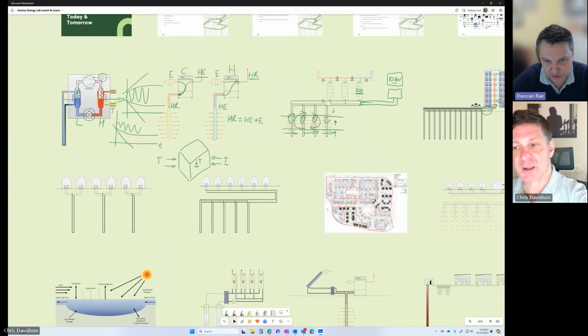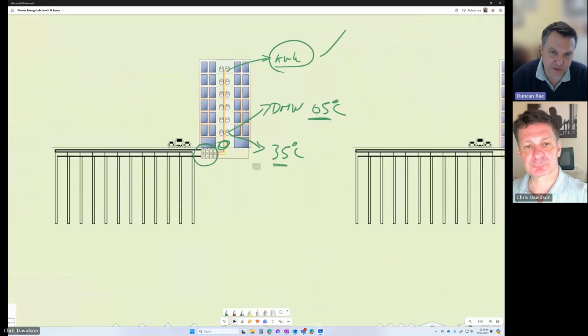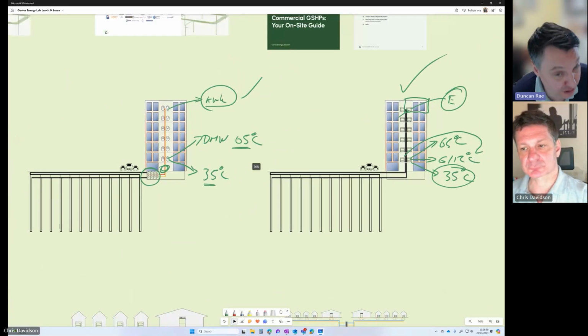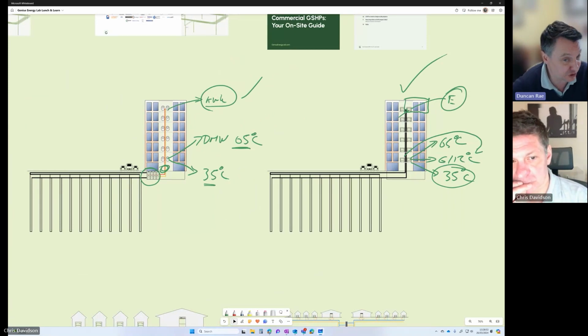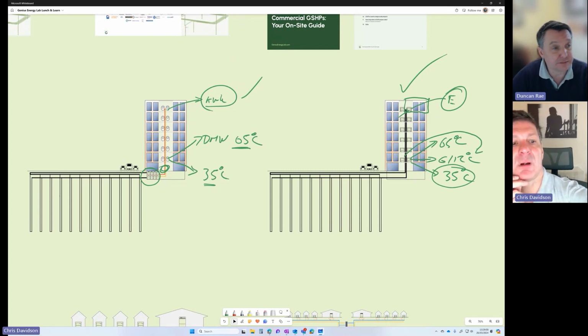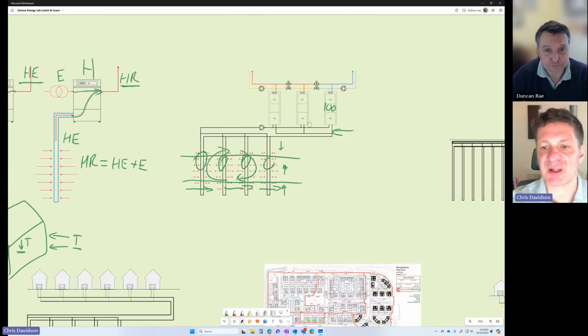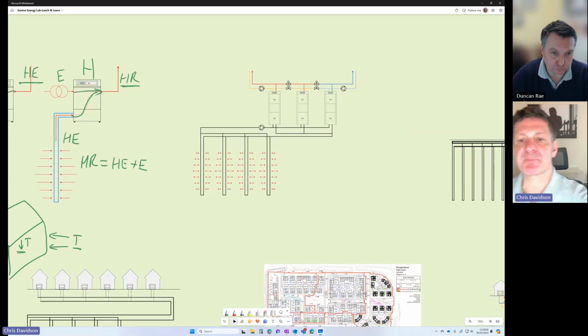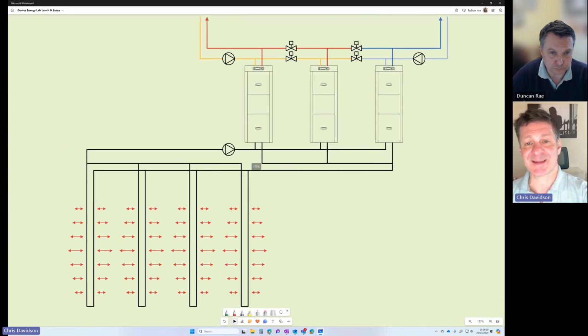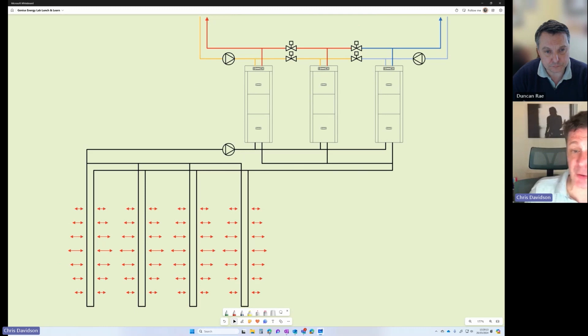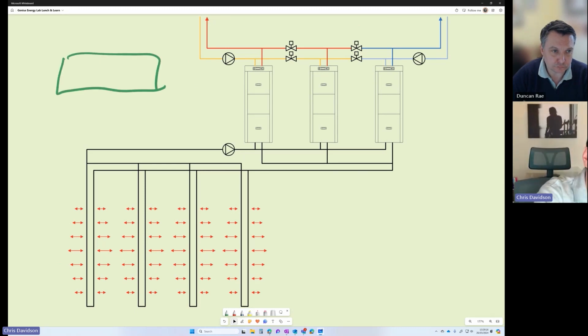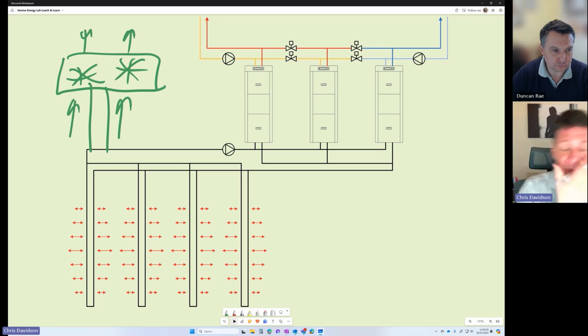Whilst you're on that slide, can you use that slide to demonstrate some of the tricks we can play in hotter climates to manage the ground loop's temperature overnight via dry air coolers, for example, when it's massively cooling dominated? Let's actually use this slide here. So let's say we've got a massively cooling dominated system. So throughout the year, we're doing more cooling than we are heating. Then what we can actually do is, if the buildings are off, it's not being operated, we can put a dry air cooler onto this ground loop, and it's got some fans in it, and they will blow hot air over a coil. If you're not familiar, a coil like a radiator in a car, and that will then allow us to exhaust heat out of that ground loop, particularly overnight.